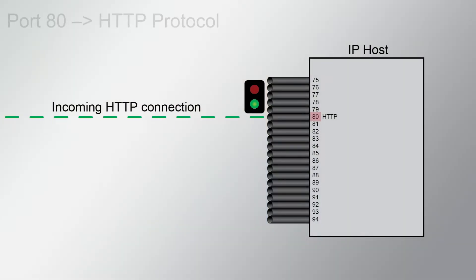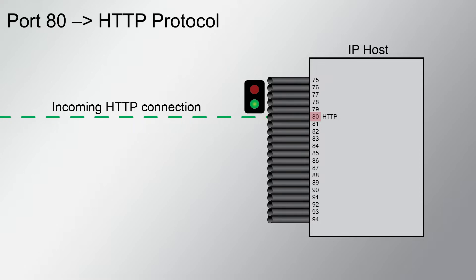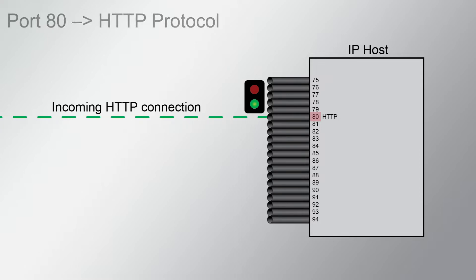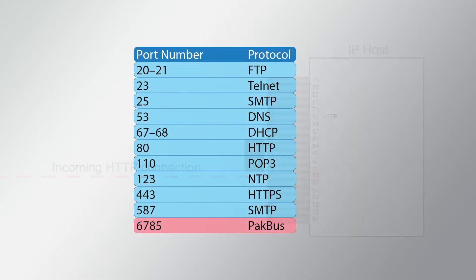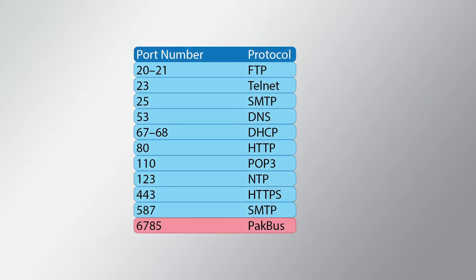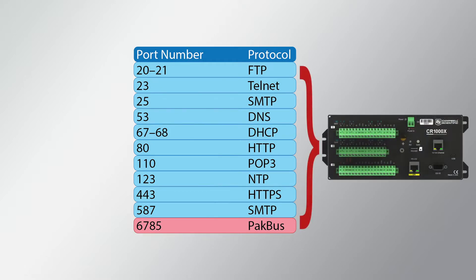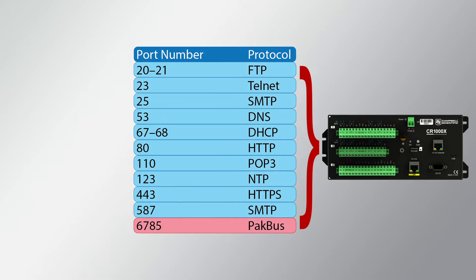For example, port 80 is used with the HTTP protocol. If an HTTP request comes in on port 88 instead of 80, the host won't know what to do with the request because it did not come in through the expected port. Here is a list of well-known ports and the network protocols they support. Port 6785 is important to Campbell Scientific dataloggers because it is the default TCP/IP port used for PakBus communications.